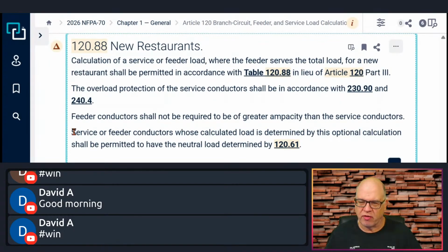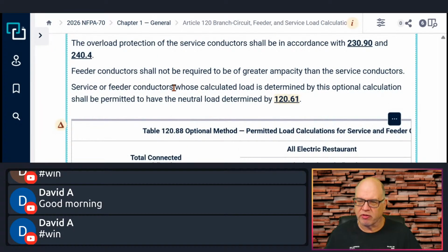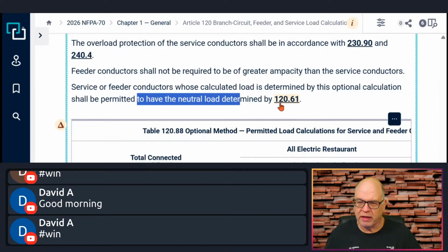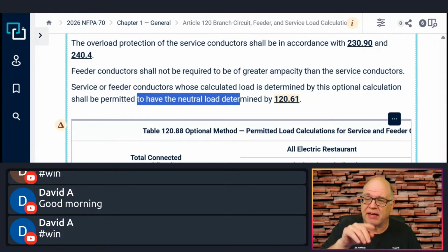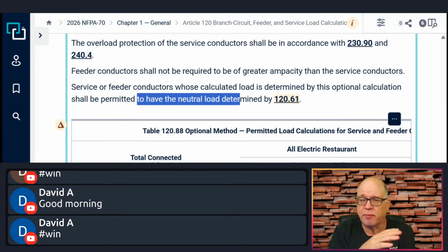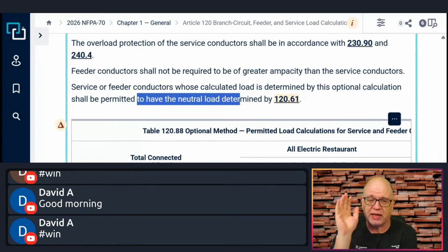Now, it says service or feeder conductors whose calculated load, this is calculated load down here, okay, is determined by this optional calculation shall be permitted to have the neutral load determined in 220.61, which is 220.61 in your 2023, 2020, and 2017. Now, the reason it makes this statement is because the neutral calculation is not found in the optional method. It's found at the end of part 3, which is the typical, normal, what we call the standard method.